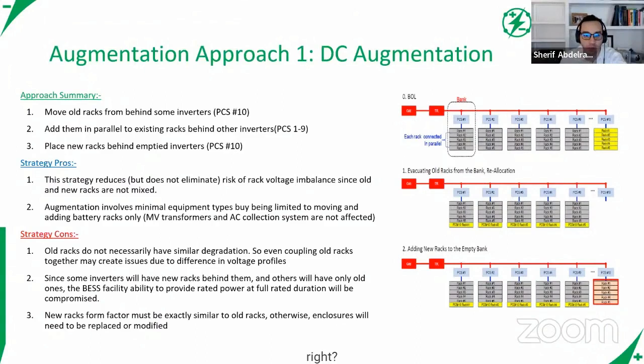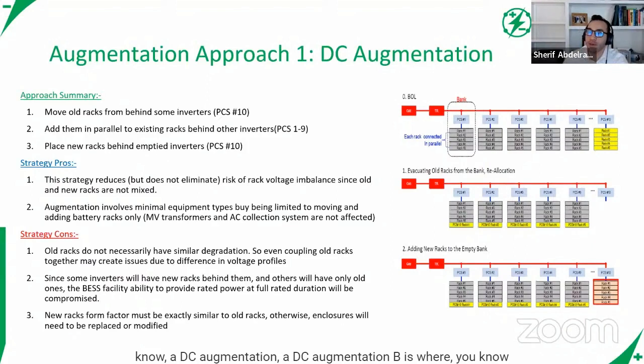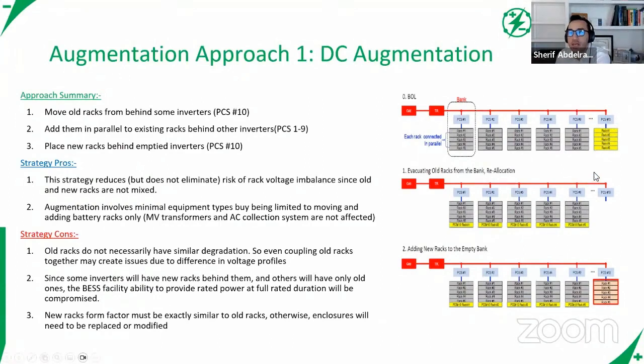Right, yeah, thanks for that. Now I'll add, in the beginning I mentioned this is DC augmentation A. DC augmentation B is where you have DC-DC converters to help with that voltage imbalance. OEMs and integrators go about this in one of two ways. Either at the beginning of the project, they assume they'll have DC-DC converters behind each inverter and on each rack - on top of each rack you have a DC-DC converter, so that rack could have whatever voltage profile it wanted, because the DC-DC converter takes care of the voltage imbalance between all racks connected to a common inverter. So that's one way.